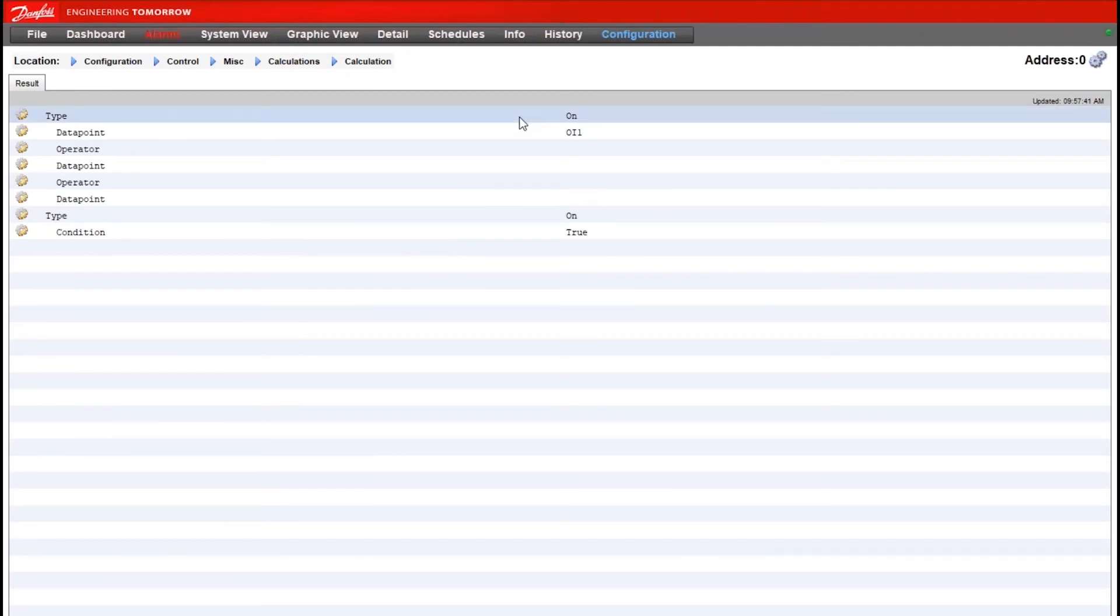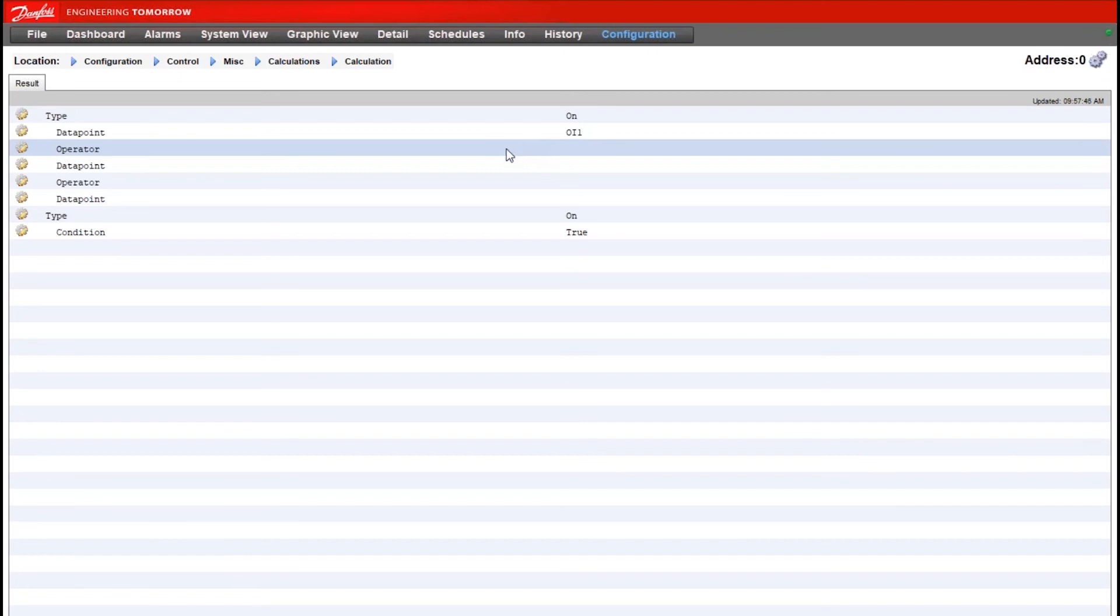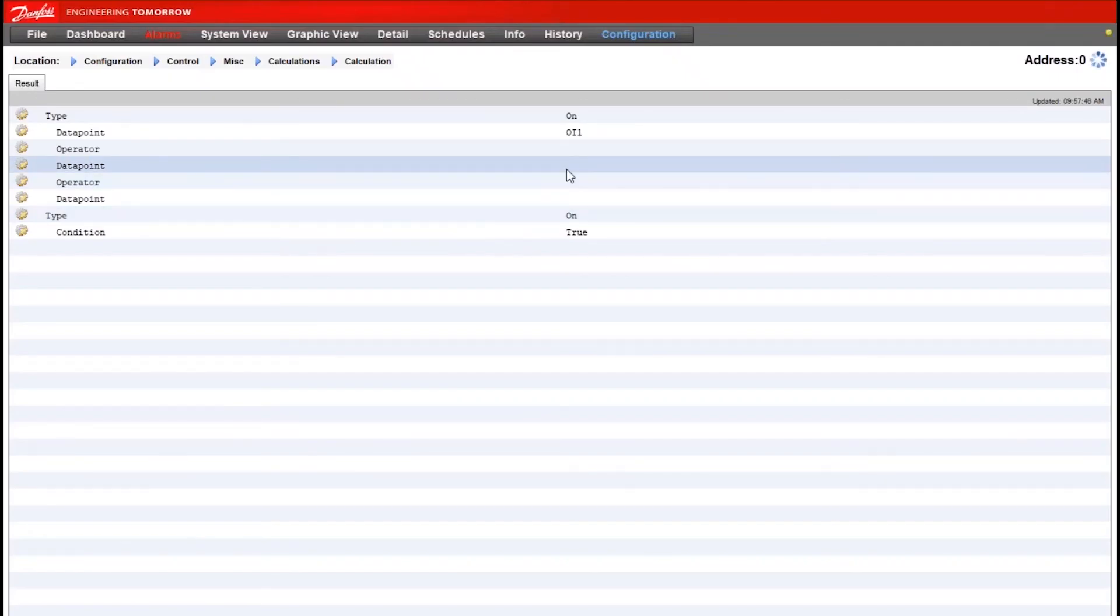The top line for type I want to change that from off to on. The type is what the calculation will do given the conditions I'm about to configure under it. And here I want to say if either one of those two relays from the case controller is on I want to turn my calculation on.